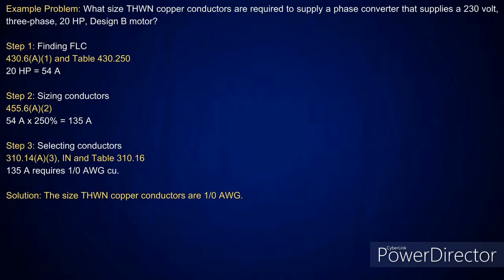One of the things, well, I'm not going to do it now, but when we get into the overcurrent protection devices, anybody that's watching this, I want you to remember what I'm talking about here. Usually I have a rule of thumb where I say if you size an overcurrent device at 125% or less, you go up to the next standard size. Any percentage above that, you drop down unless it states otherwise. And I give you two instances when I give that rule of thumb. I said you really have to look at phase conversion because it tells you it has to protect the conductors. In this case, they have them going up to 250%, which is 135 amps, which requires a 1-aught conductor in the 75 degree C column, which is good for 150 amps. But when I size the overcurrent device, instead of dropping down, I would put a 150 amp overcurrent device there because in this section, it tells you you have to protect the conductor.